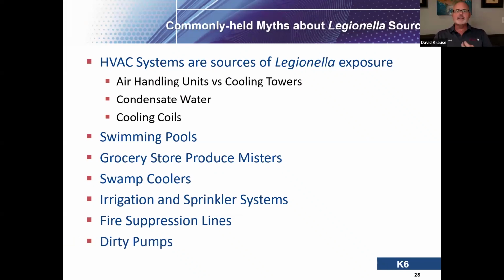Dirty pumps. How did the Legionella get into this building? Pumps were dirty is the assertion or claim often made, but not really one we can rely upon. That Legionella is a building-related problem, that is true. That it's not in the municipal water supply, that is often an unfounded statement. We find this in many municipal water systems on a repeated basis all across the country doing testing, so it is recognized to be a source of inoculation to these buildings.